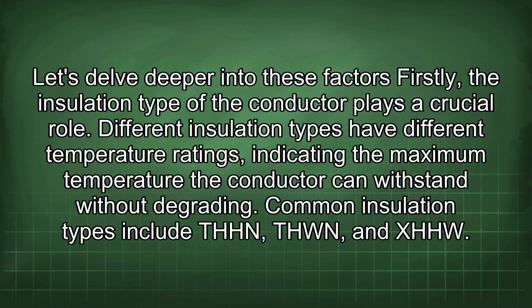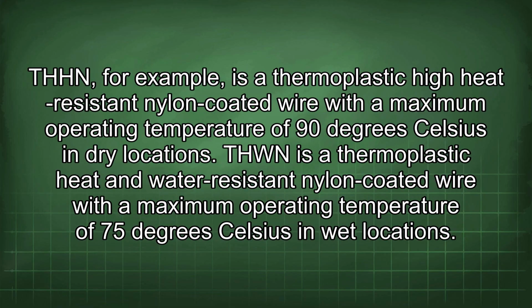Firstly, the insulation type of the conductor plays a crucial role. Different insulation types have different temperature ratings, indicating the maximum temperature the conductor can withstand without degrading. Common insulation types include THHN, THWN, and XHHW. THHN, for example, is a thermoplastic high heat resistant nylon coated wire with a maximum operating temperature of 90 degrees Celsius in dry locations. THWN is a thermoplastic heat and water resistant nylon coated wire with a maximum operating temperature of 75 degrees Celsius in wet locations.